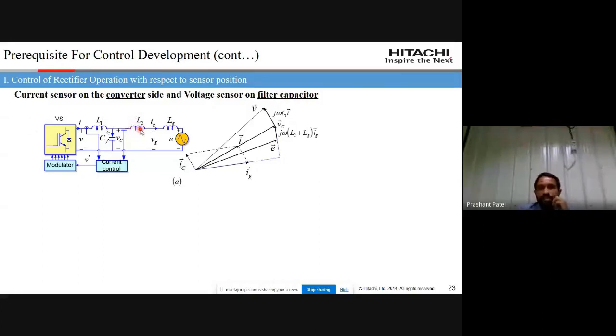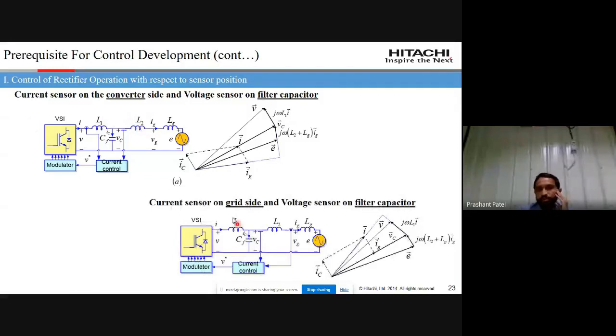Another option: you can put your current sensor on the grid side and voltage sensor on the filter capacitor. Then you get unity power factor between this VC and this IG. From the phasor diagram it's clear you can get unity power factor at this point.